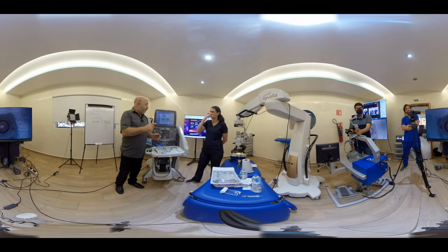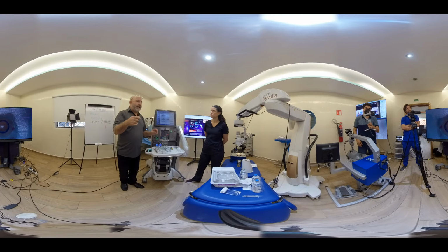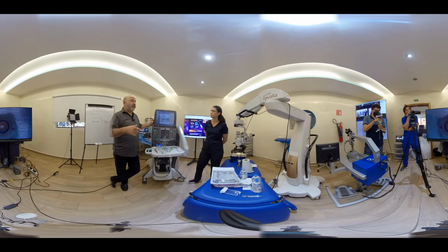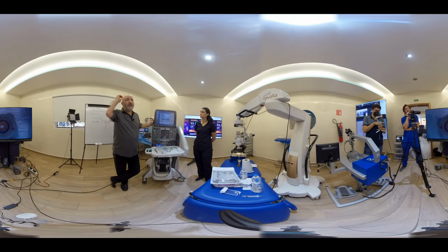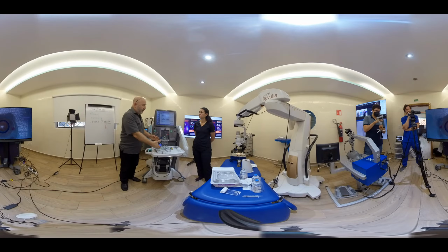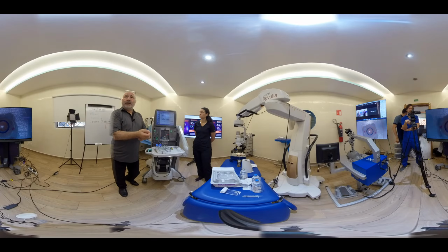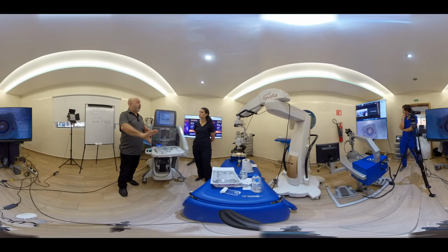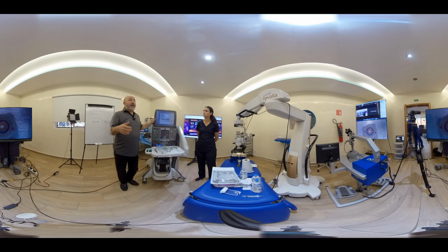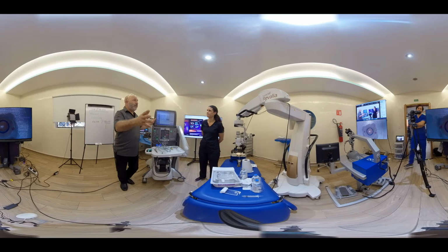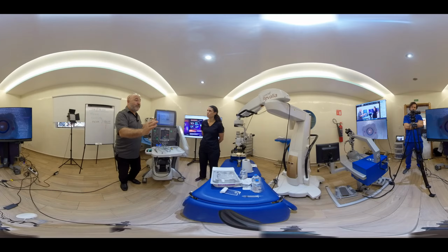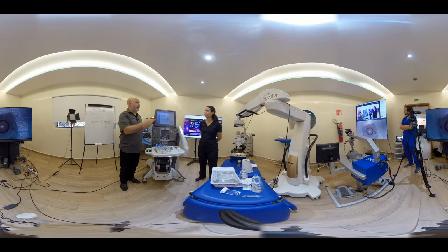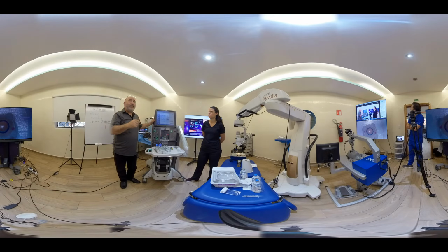So you would have seen, as you get smaller and smaller gauge, the effect of that is dramatic. In 25 gauge, you'll start noticing regurgitation if your patient eye level is not set. And in 27, it's the same volume in the line that's pushing down a smaller hole, a smaller shaft, so it comes out at a greater velocity. So you notice it even more in 27 if your patient eye level is not set. And then you'll also notice it, let's say you've done a vitrectomy and you've got this floating flap that's hinged and you want to trim it or something. When you go to touch the pedal to try and trim it, it blows it away. That's regurgitation coming down the system. So if you set the patient eye level, you get the aspiration benefit and you get the correct IOP.